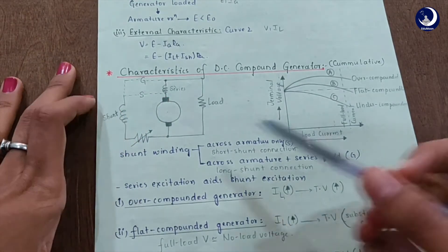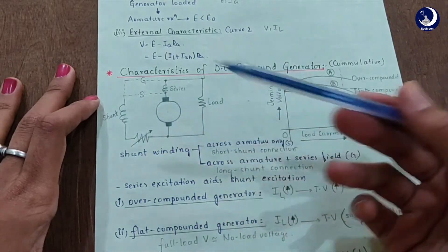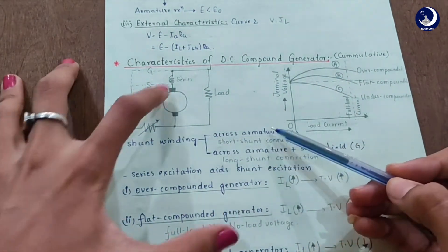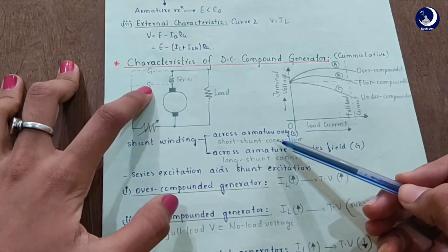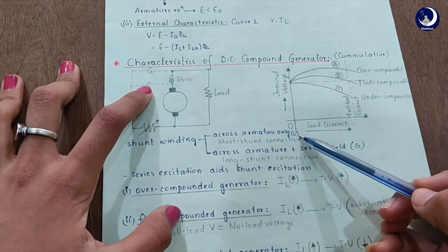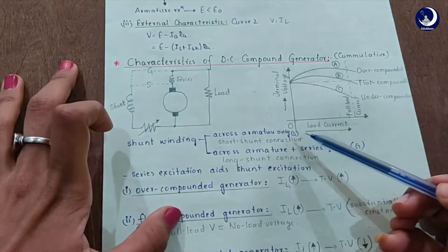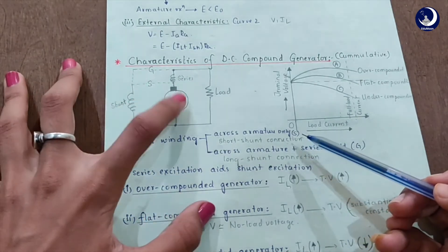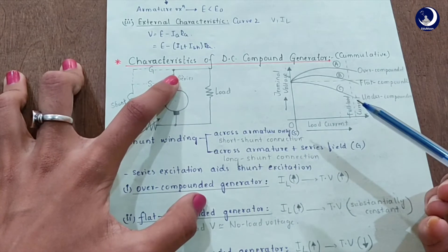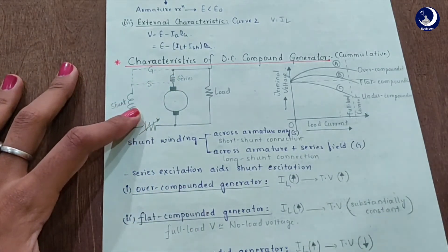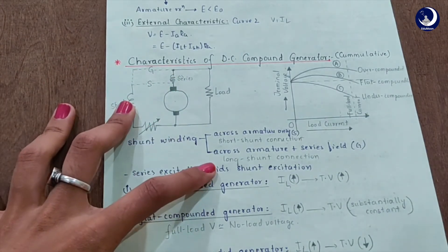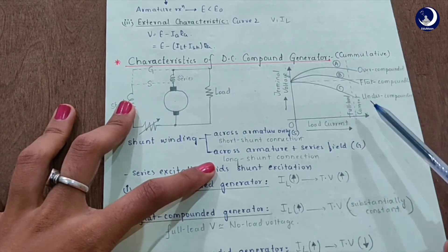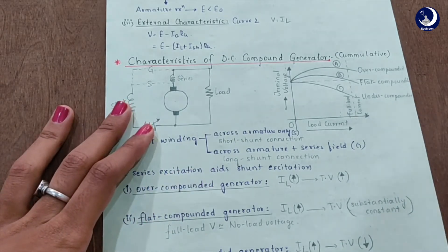The shunt winding can be connected in two ways. If you connect it across the armature only, that is the short shunt connection, denoted by capital S. If you connect the shunt winding across both the armature and the series field, we call it the long shunt connection, denoted by capital G. This graph shows the characteristics of the DC compound generator.